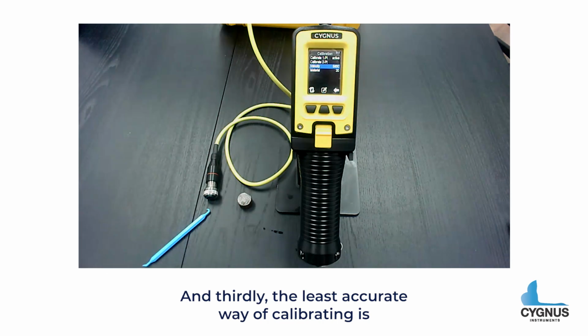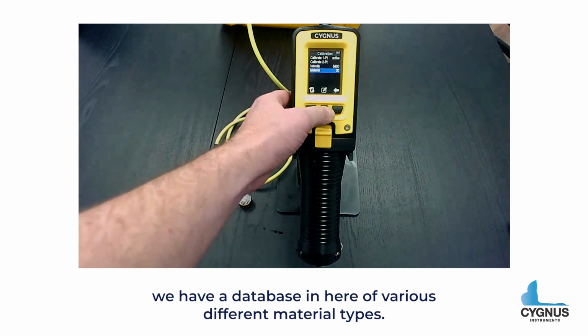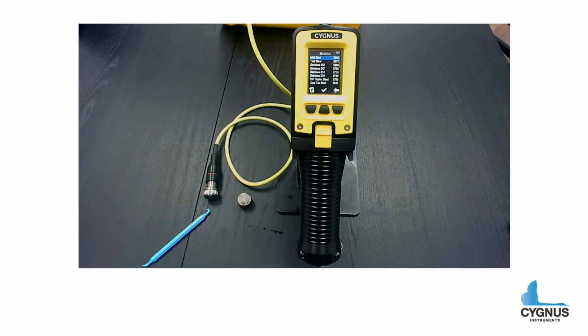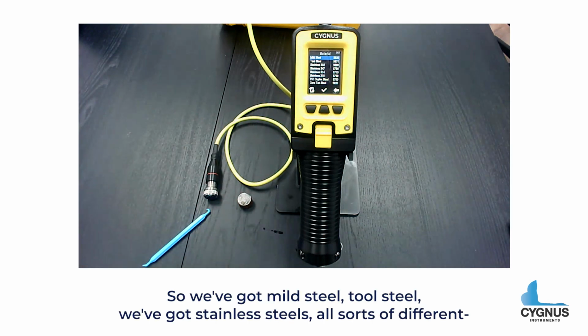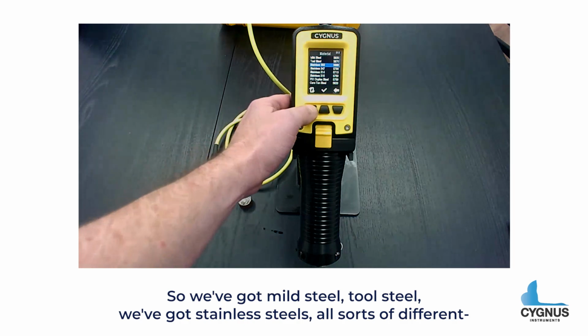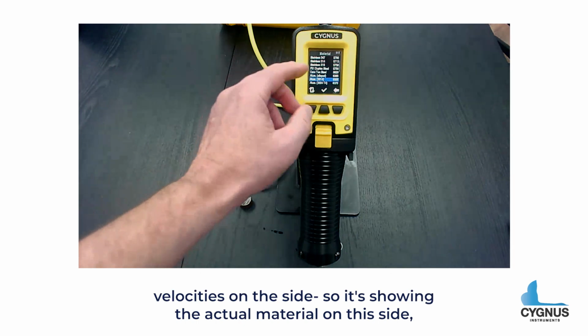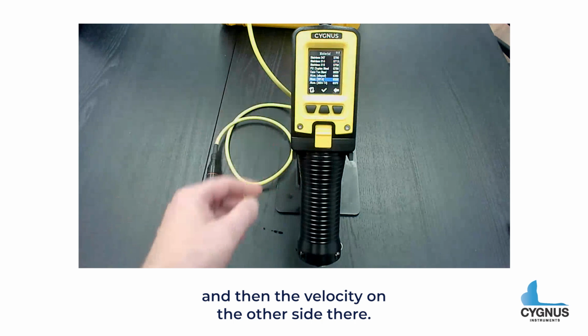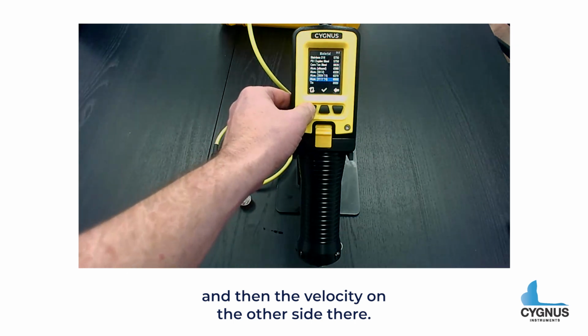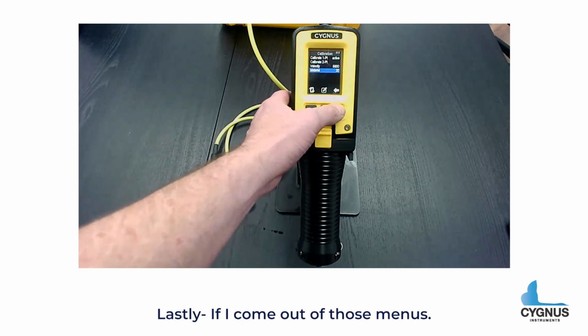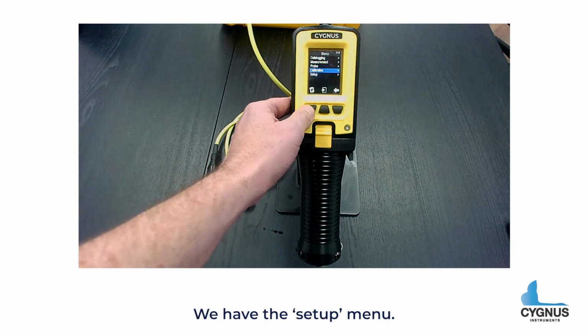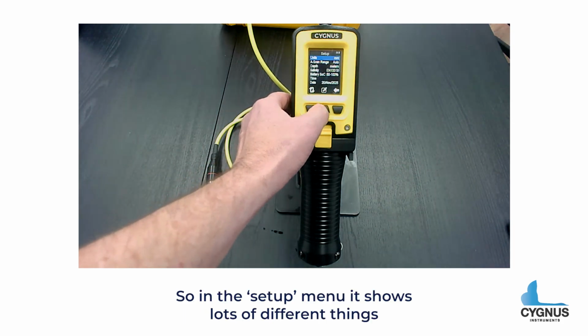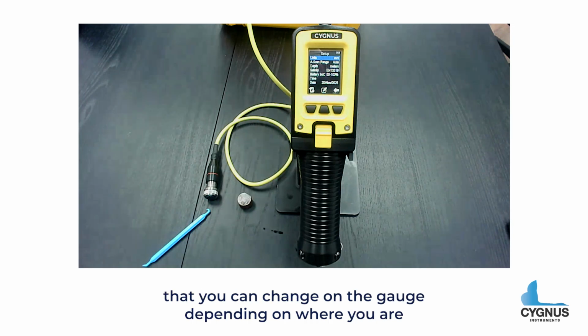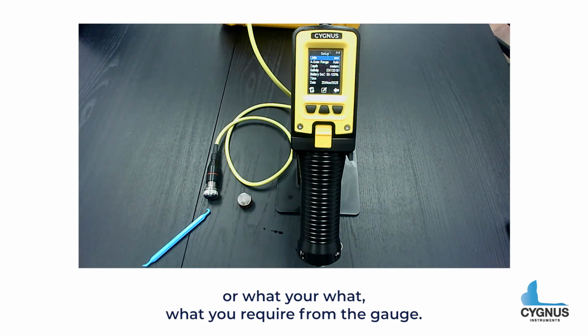And lastly, the least accurate way of calibrating is we have a database in here of various different material types. So we've got mild steel, tool steel, stainless steels, all sorts of different velocities. It's showing the actual material on this side and then the velocity on the other side there. Lastly, when I come out of those menus, we have the setup menu. In the setup menu, it shows lots of different things that you can change on the gauge depending on where you are or what you require from the gauge.